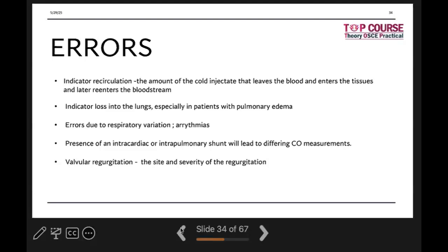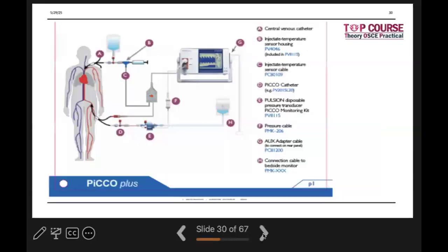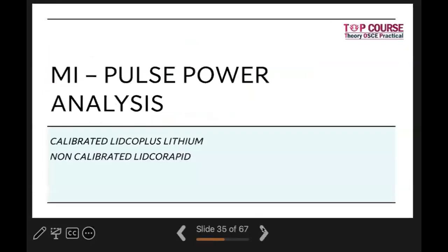So we just saw minimally invasive devices that use transpulmonary thermodilution and pulse contour analysis. That is PiCCO, VolumeView, and LiDCO plus. Now, there is one small variation with respect to LiDCO plus. We know that LiDCO plus uses pulse power analysis rather than pulse contour analysis, but LiDCO plus also intermittently calibrates its system using lithium rather than cold saline, and that is why the name.